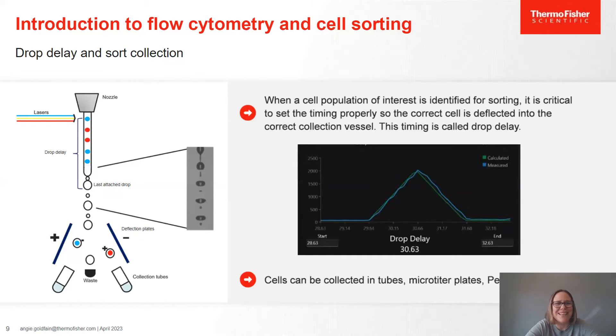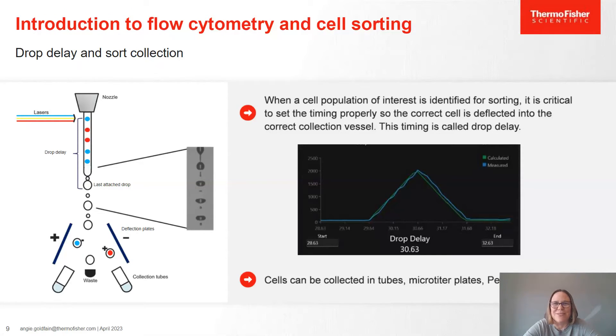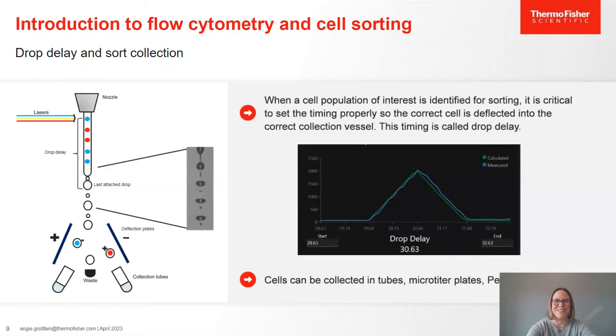Once we've calculated that timing, we apply a charge to the last attached droplet that we've accurately timed, let that droplet break off from the rest of the stream, and then it goes through electrostatic deflection plates. Negatively charged cells move toward the positive plate and positive cells toward the negative, directing them into whatever sort collection vessel is below. We also catch the waste, which can be decontaminated safely. Different instruments can sort at different speeds — some create 30,000 droplets per second, some 90,000 or 100,000 — which dictates how fast you can sort cells.